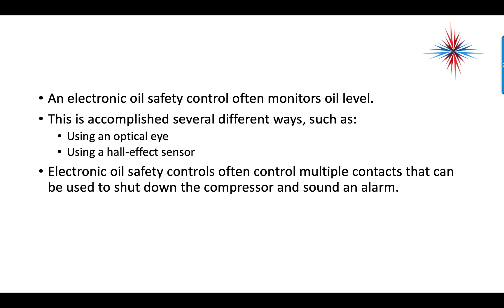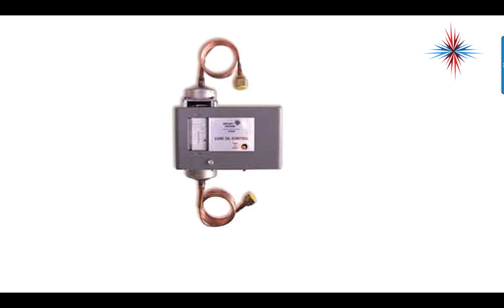An electronic safety control often measures oil level, accomplished several ways such as using an optical eye or a Hall effect sensor. Electronic oil control safety controls often control multiple contacts that can be used to shut down the compressor and sound an alarm. Here is an example of a mechanical oil pressure control: one side goes to the pump, the other goes to the low side of the system on the suction line. The adjustment dial is used to set what the net oil pressure should be, and there's also a manual reset button in the center.